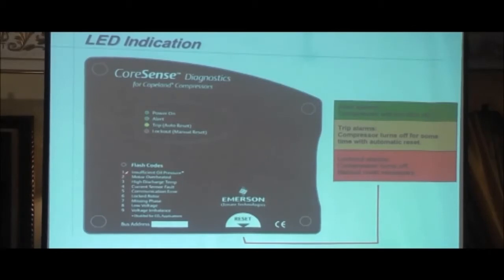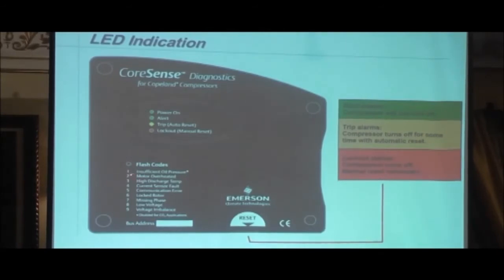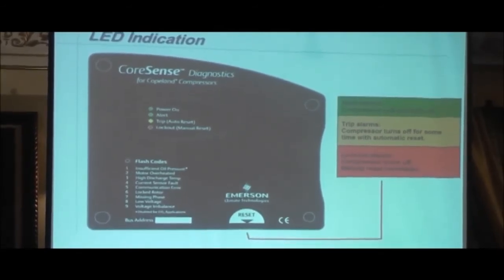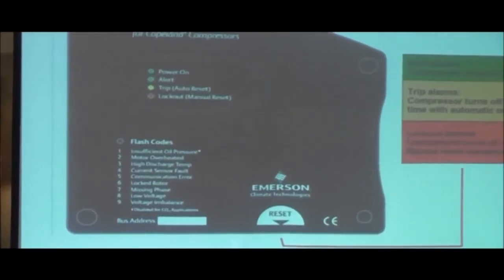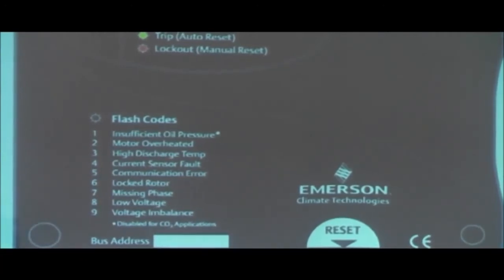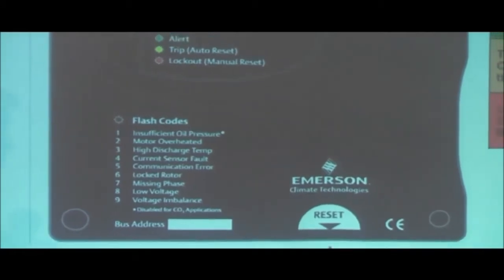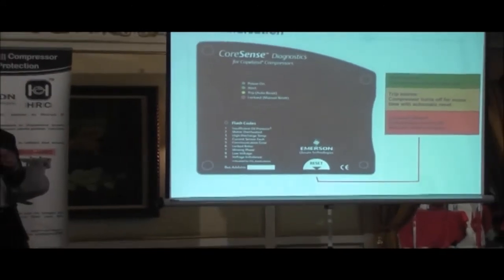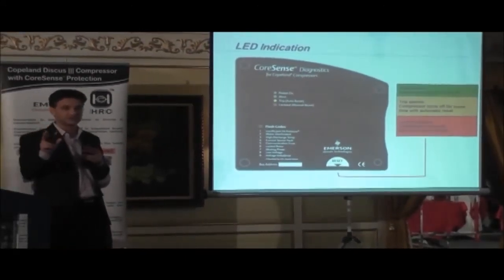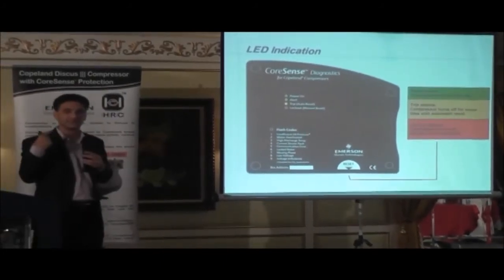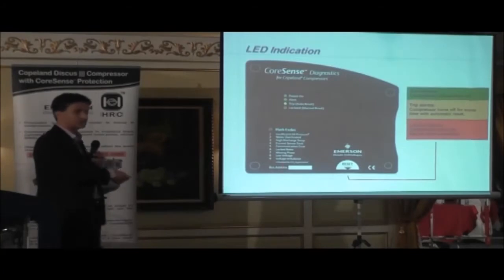Okay. These are the flash codes. So, if I have, let's say, a missing phase condition, when it trips the first time, the flash code will blink 7 times on yellow. Right? It will then try and reset. At the 10th attempt, it will go into manual lockout, and the yellow LED will go to red, and the red will blink for 7 flash codes. So if you have a trip condition and you get to site, by counting the number of flash codes, it will tell you what is wrong with the compressor.